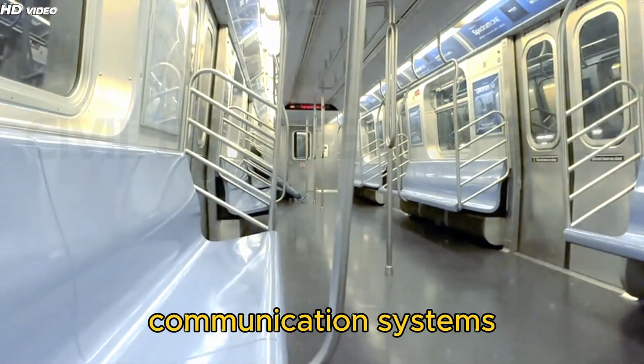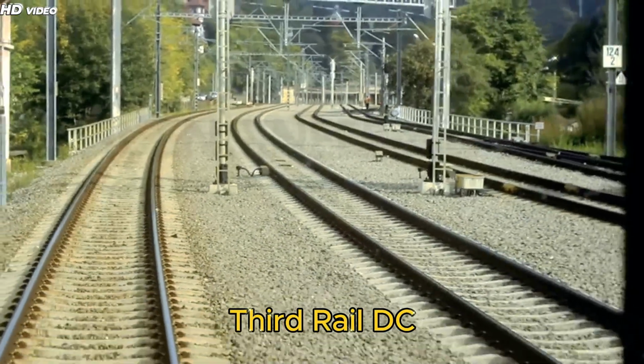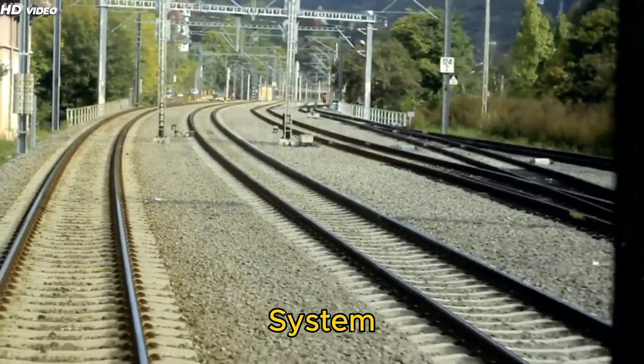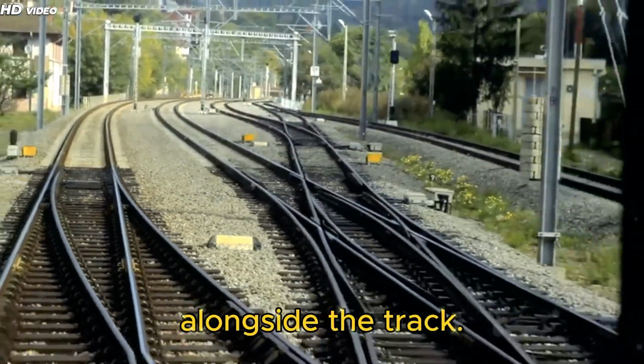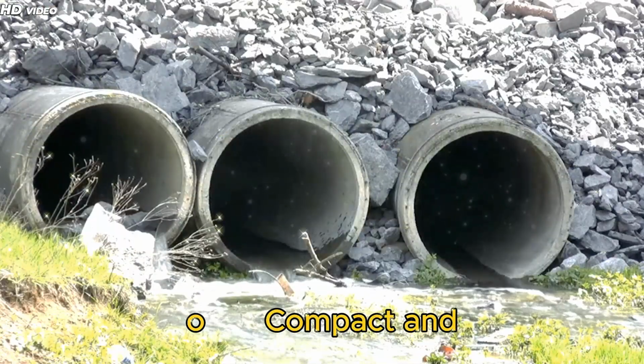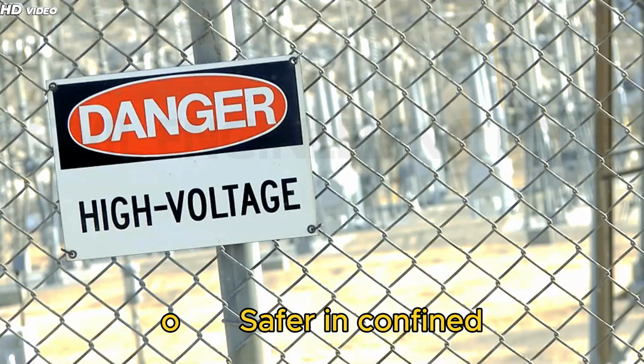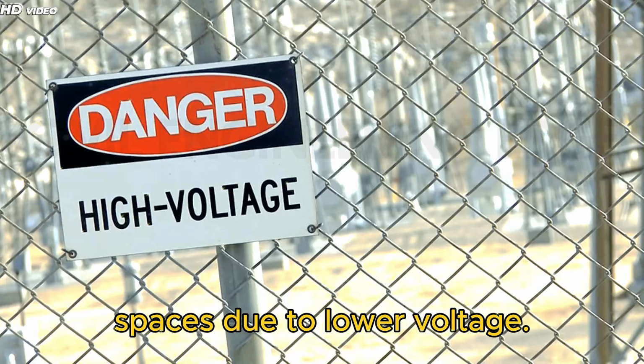Types of electrification systems. 1. Third rail DC system, typically 750 volts DC. A power rail runs alongside the track. Compact and suitable for tunnels. Safer in confined spaces due to lower voltage.